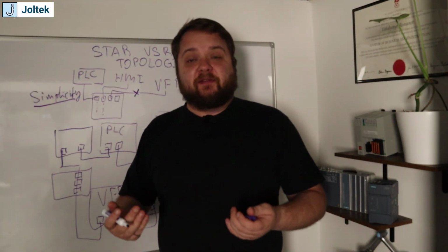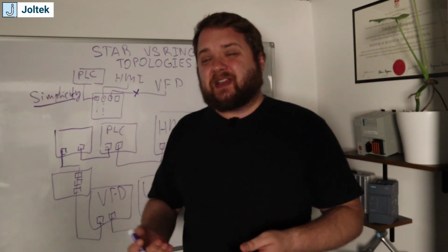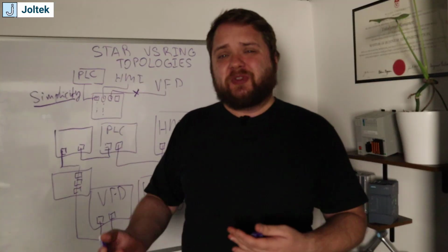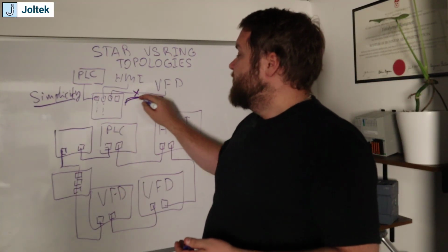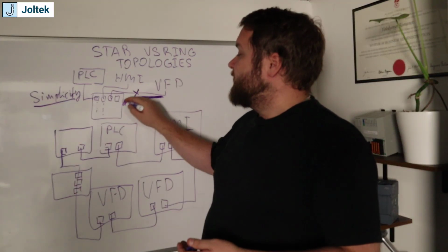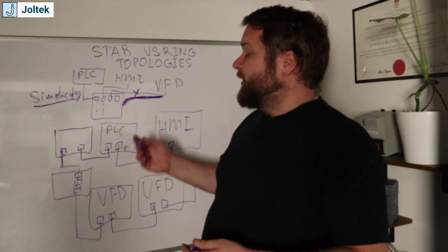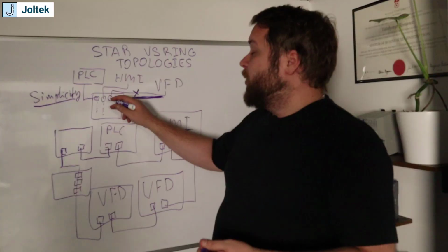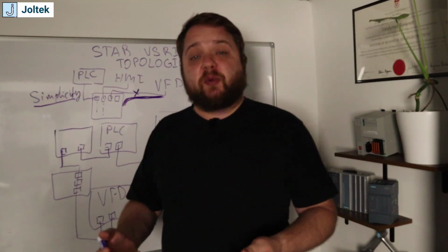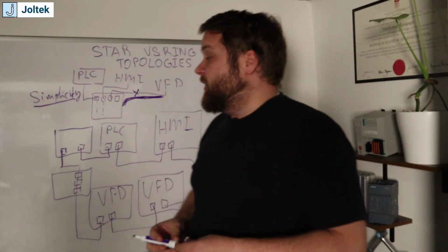Of course, if somebody cuts the cable in two, it's no longer going to be able to send the signals, but also if there's problems with the traffic, perhaps it is next to a very large power line. So imagine that this is a 480 line that is causing this VFD to lose some of those signals. The VFD will intermittently fail, and thus not be able to receive whatever configuration or whatever parameter changes you are sending to it, or receiving or reading from the VFD.